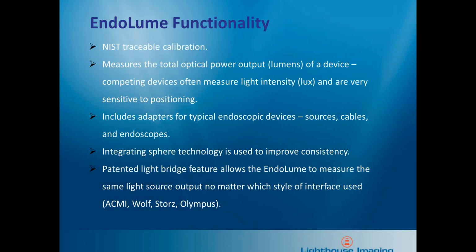...when you have those sources, as I showed earlier in the presentation, that have a turret or multiple port setting, the output from those different ports, if you try to measure it with a lux meter, can vary by a factor of 5 or 10 depending on which one you're using. So you'll get a totally different answer just by changing the turret setting.